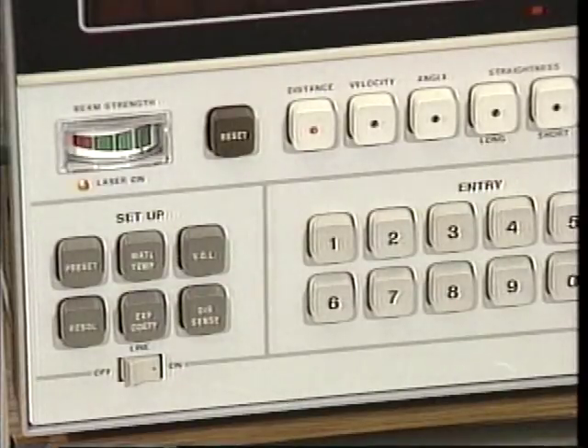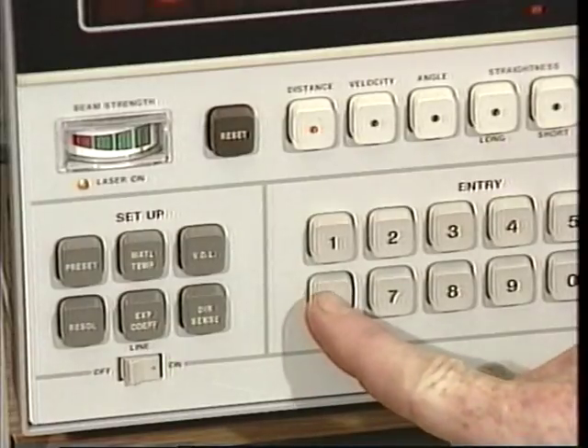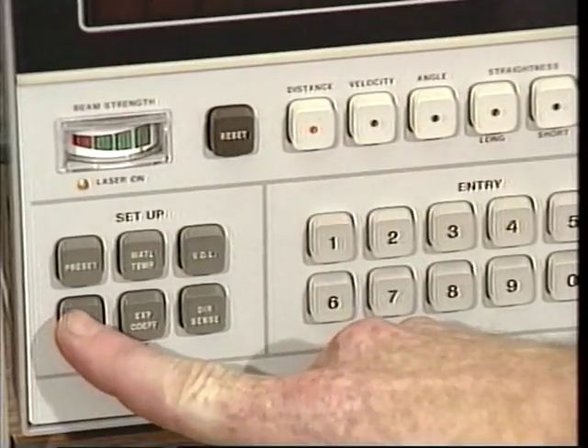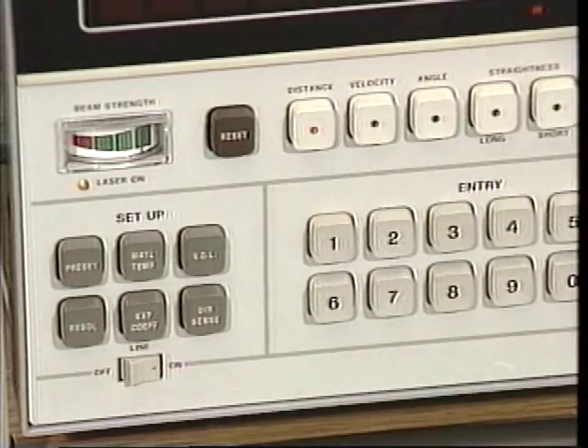To select the desired resolution, use the numeral entry keys to enter the number of decimal places desired, then press the resolution key. In metric mode, the maximum available resolution is 5 decimal places, or 10 nanometers. In English mode, the maximum available resolution is 6 decimal places, or 1 microinch. Entering a negative resolution causes the normal data smoothing to be removed.